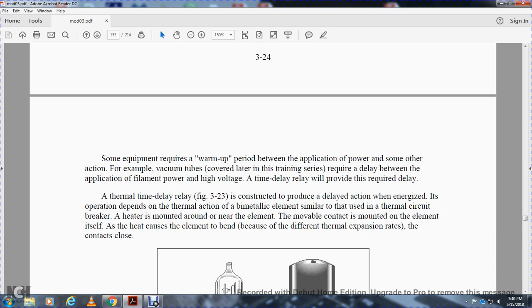A thermal time delay relay, figure 3-23, is constructed to produce the delay action when energized. The operation depends on thermal action of a bimetallic element, similar to that in a thermal circuit breaker. A heater is mounted around the element. The movable contact is mounted on the element itself.